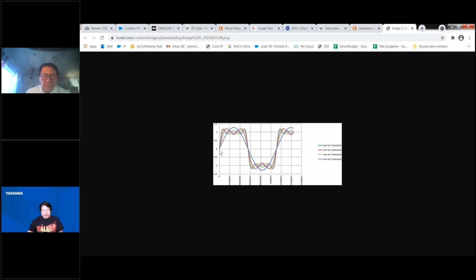But what Craig's talking about in terms of the smooth sine wave versus the bumpy sine wave, and what it does to the submersible motor operation, what it does to any motor operation, frankly, is if you look at the blue line here, that's the perfect sine wave. And if you look at these various colored waveforms other than blue, you'll see that they're not quite sinusoidal. And this is an almost sine wave, which is what standard VFDs that we've been using since 1983 accomplish without filters. Now, you get back to the blue waveform when you put a sine wave filter on the output of the VFD to the motor.